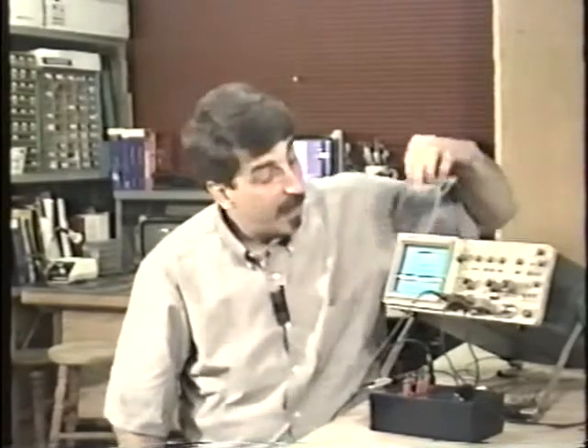Not only can I select a faster sweep speed, but on the top I can see what part of the waveform I'm illuminating. Look, the B sweep is a little bit brighter. Watch as I increase the B sweep speed. I'm selecting a smaller piece of this waveform to look at. If I turn down the intensity, you can really see that what's illuminated here is what's down here on the B sweep.